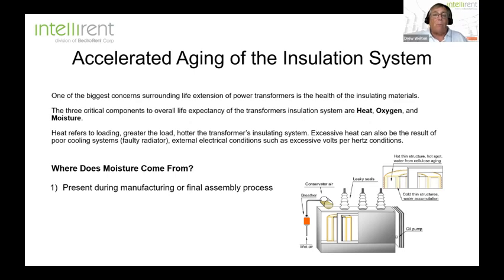Well, where does moisture come from? Moisture can be present during the manufacturing or the final assembly process. Generally, they'll take the transformer, just the windings themselves, put them in a vapor phase chamber and dry the insulation. It's like an oven. It just cooks it and draws the moisture out. So you start with dry insulation. But what happens after that? It gets put in a tank, transported via rail or a flatbed, and delivered to the customer. At that point, they'll attach the radiators, they'll attach the bushings, they'll fill it with oil, and there's always a chance that you can get water going into the transformer tank during those processes. The other is leaky gaskets around the bushings or the radiators. You know that whenever you have mineral oil leaking out of the transformer, you know for sure moisture is going in. So that's very important to be aware of.